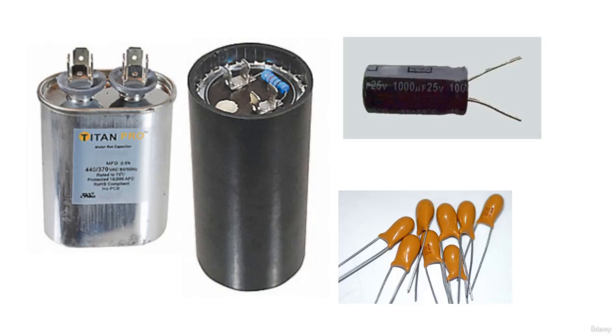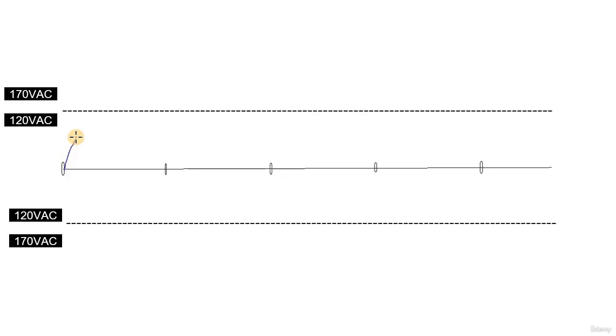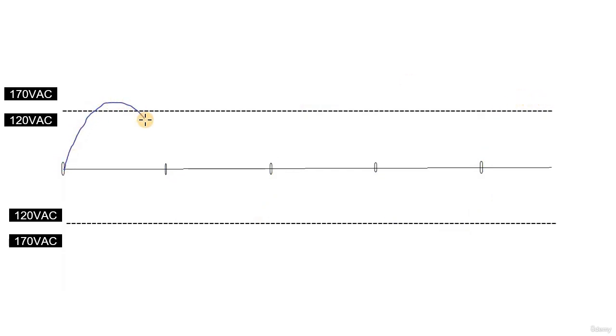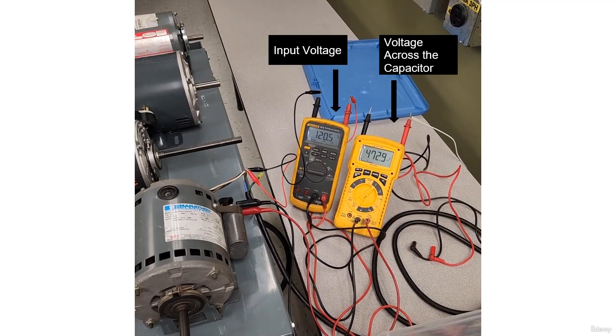You will see capacitors in many shapes, sizes, and many different materials. I won't go into the exact construction, but they function similar to batteries. They will store the applied charge. In AC circuits, remember back when I talked about your meter reading RMS, and when we apply AC voltage, we see 120 volts, but the actual peak voltage is 170 volts. Your capacitor will capture the entire 170 volts and give you a boost for starting motors.